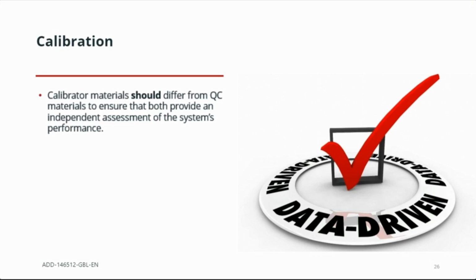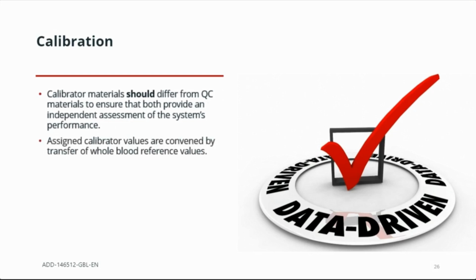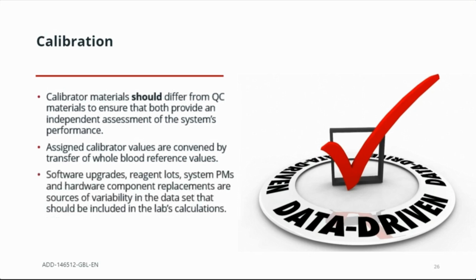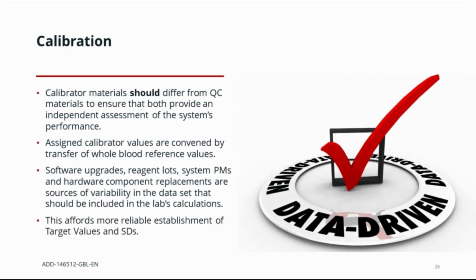It's good lab practice for manufacturers to value assign and provide target values that are conveyed by transfer of whole blood reference values in their methods. And taking into consideration different software versions, reagent lots, system PMs, and hardware component replacements, all of these can be sources of variability. So that should be part of our data set that helps us understand whether or not we truly need to calibrate. This affords overall a more reliable establishment of our target values and standard deviations as we move forward.